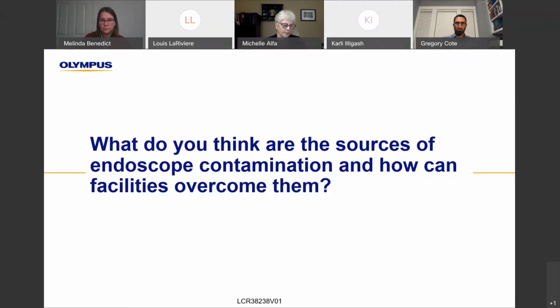And the other one that can occur is actually the inadequate storage of endoscopes, where if there's wet storage there's an opportunity for any organisms, whether they're environmental or from a previous patient procedure or from handling, if there's moisture in the channels, those organisms can replicate and can certainly start to form biofilm. And if this is done on a repeated one after another basis, ultimately there can be enough buildup that the disinfection doesn't work anymore.